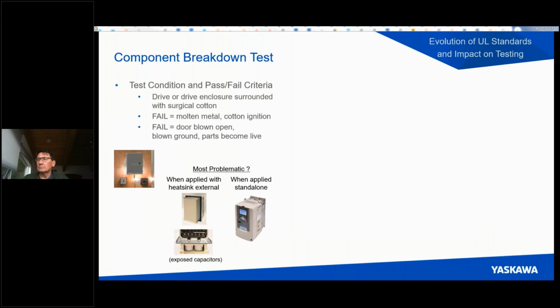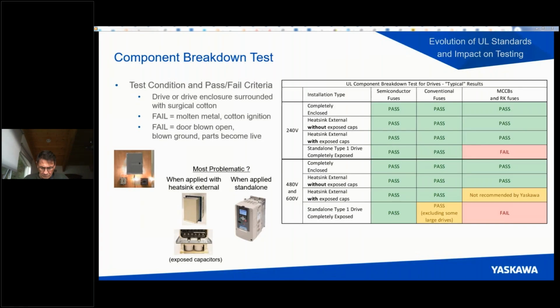Now this is most difficult to pass, either when the drive is mounted standalone by itself, or with its heatsink external for drives that have exposed capacitors. However, based on the type of overcurrent protective device used, we also have solutions that will pass for these installation conditions. The following chart summarizes the typical results from many common installation types with different overcurrent protective devices. On the left side of this chart, from top to bottom for both voltage classes, you'll notice 4 installation types. Those being completely enclosed, 2 cases of enclosed with external heatsink, and also standalone where the drives are completely exposed.